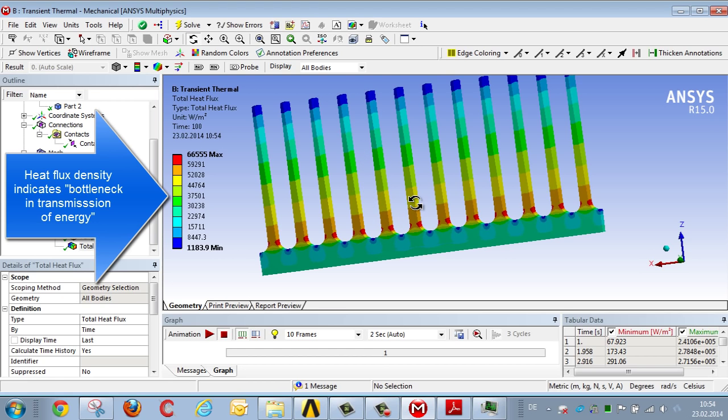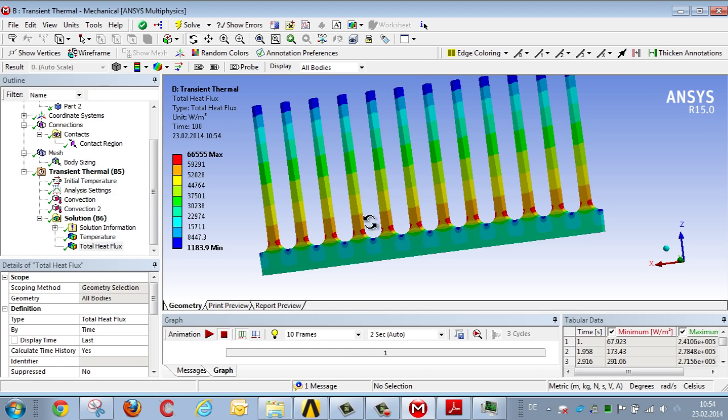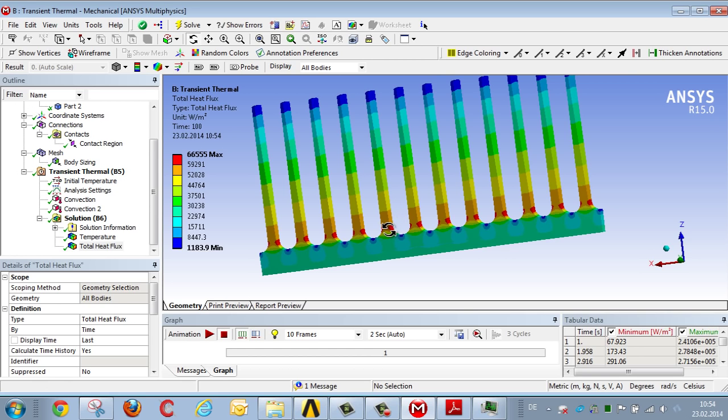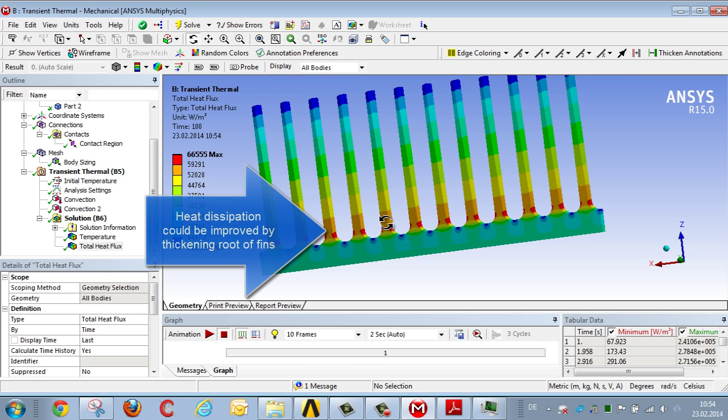The fins have a very large surface area, allowing a lot of energy to be discharged. There's a bottleneck, a high heat flux density, at the exact point where the fins begin, meaning it's difficult for the energy to enter the large surface area of the rib. You could improve the heat dissipation in this region by thickening this part of the fin somewhat.